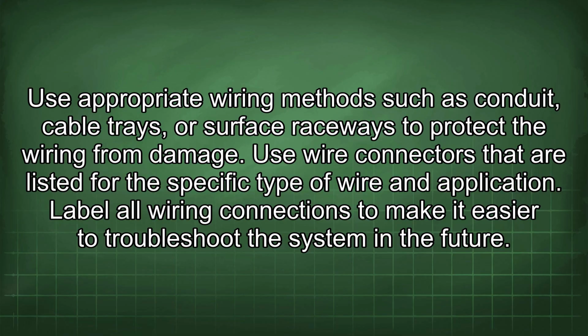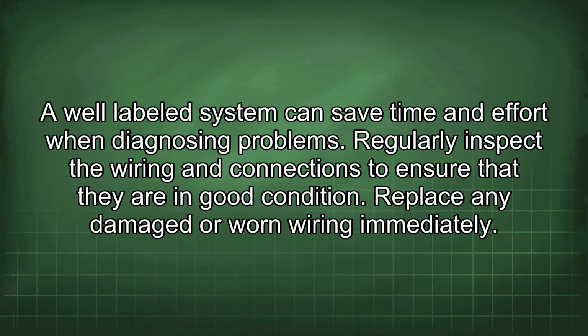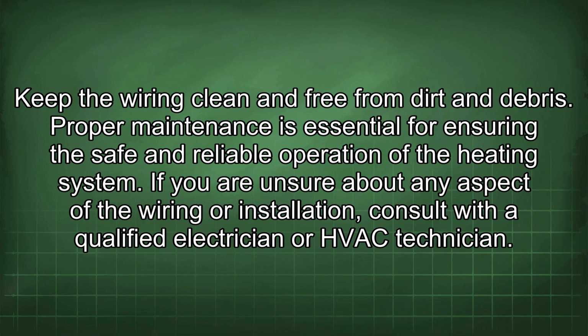Use wire connectors that are listed for the specific type of wire and application. Label all wiring connections to make it easier to troubleshoot the system in the future. A well-labeled system can save time and effort when diagnosing problems. Regularly inspect the wiring and connections to ensure that they are in good condition. Replace any damaged or worn wiring immediately. Keep the wiring clean and free from dirt and debris. Proper maintenance is essential for ensuring the safe and reliable operation of the heating system.